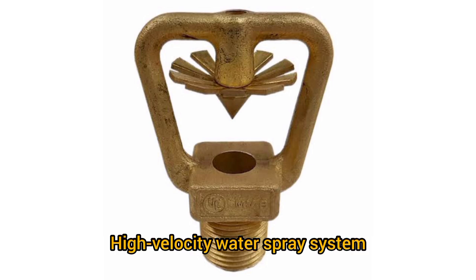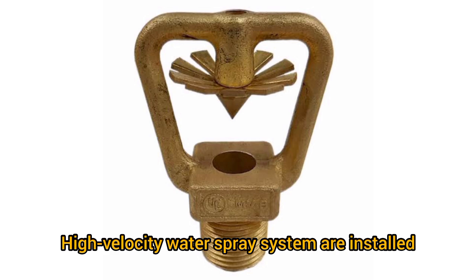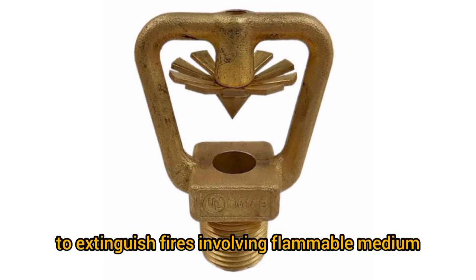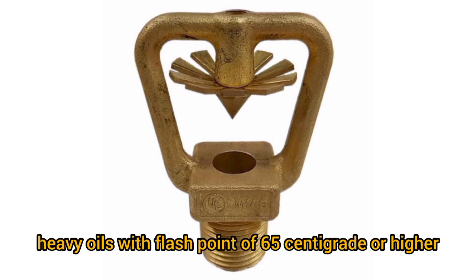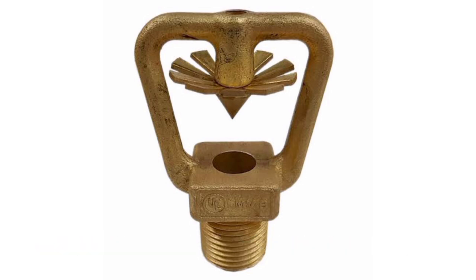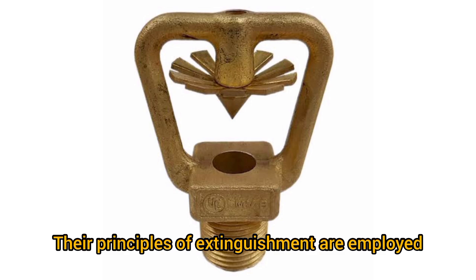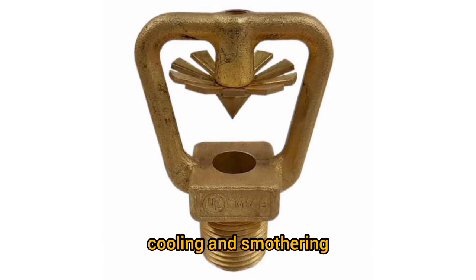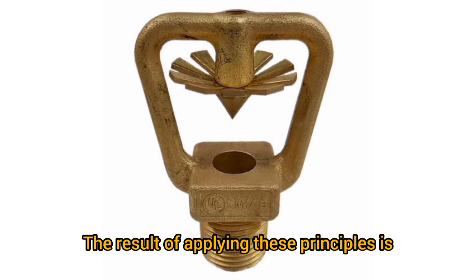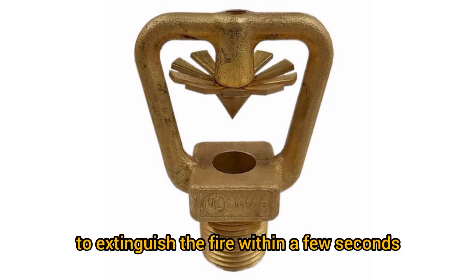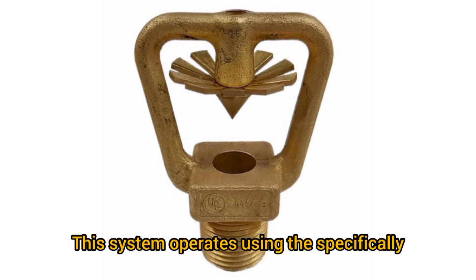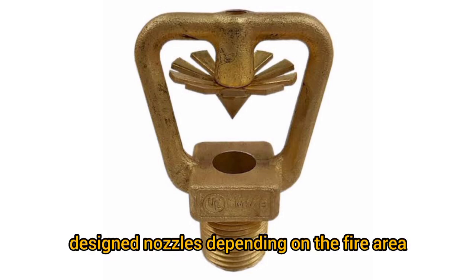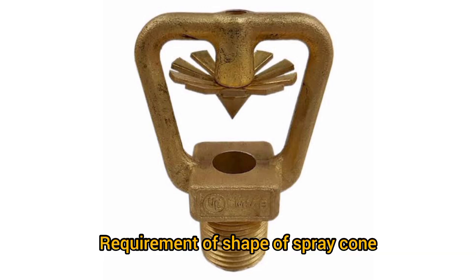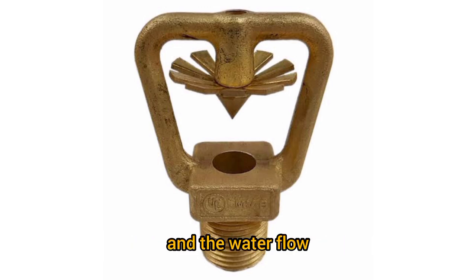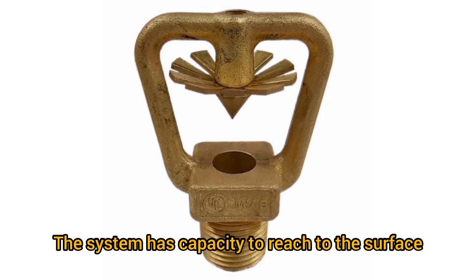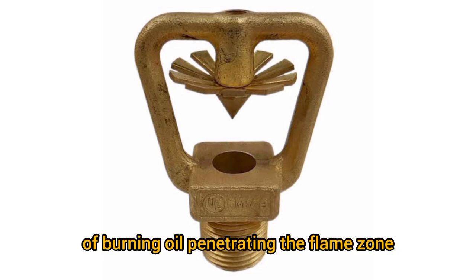High-velocity water spray system. High-velocity water spray systems are installed to extinguish fires involving flammable medium-heavy oils with flash point of 65 centigrade or higher. Three principles of extinguishment are employed in the system: emulsification, cooling and smothering. The result of applying these principles is to extinguish the fire within a few seconds. This system operates using specifically designed nozzles depending on the fire area, requirement of shape of spray cone and the water flow. The system has the capacity to reach the surface of burning oil, penetrating the flame zone.